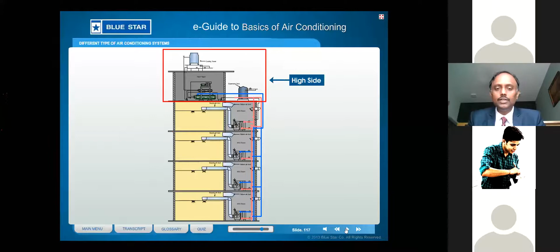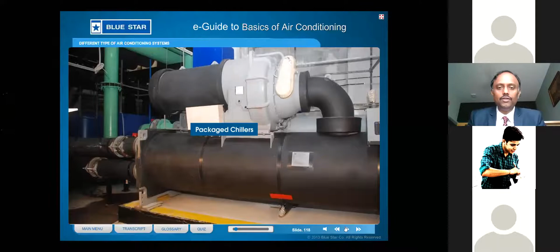That is very important. In the chilled water system, the high side is nothing but the chillers, the cooling towers, and the chilled water pumps. The AHUs and the ductings, what you see inside the conditioned premises, are called the low side. This is a picture of very large chillers kept inside the plant room. This is a centrifugal chiller, of some 1500 to 2000 tons capacity. This is the chilled water pumps.